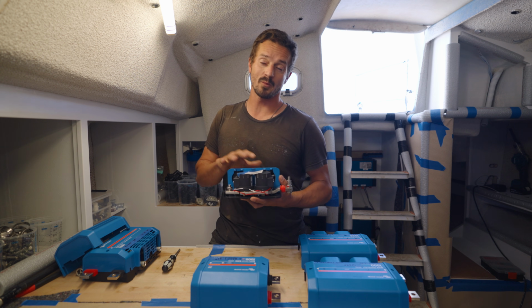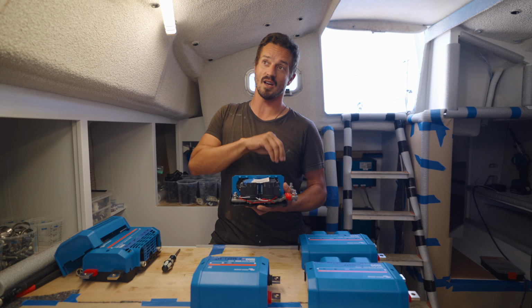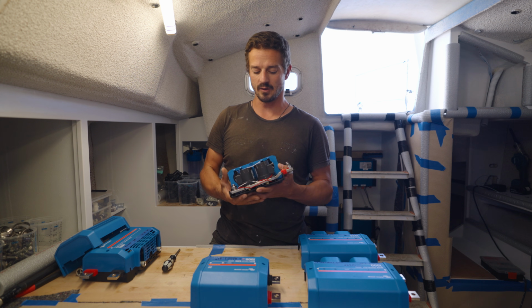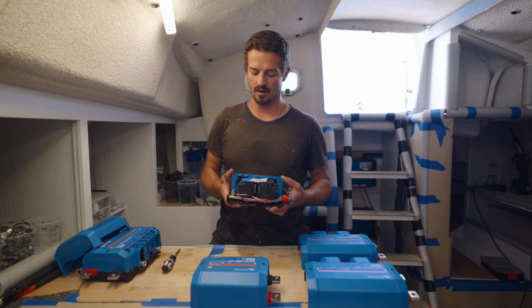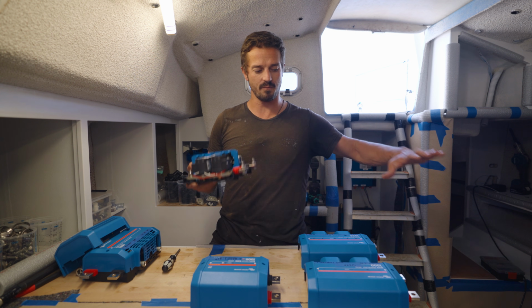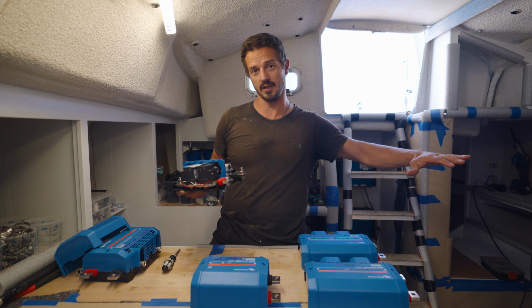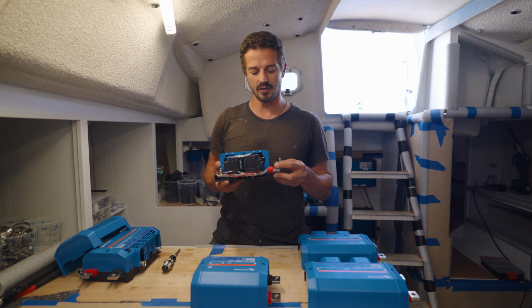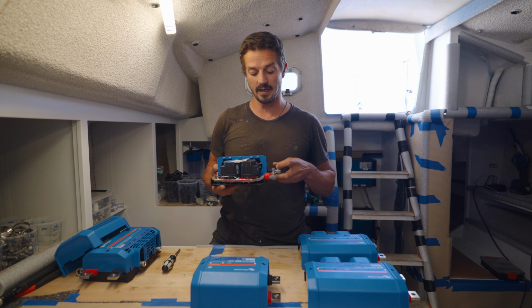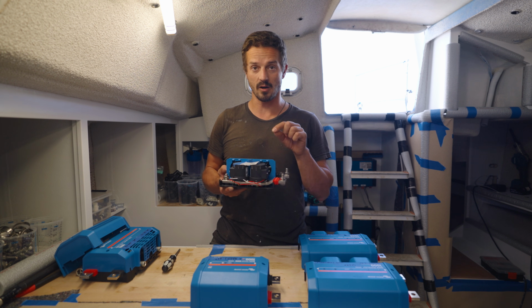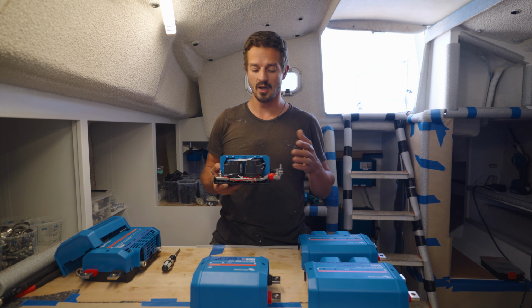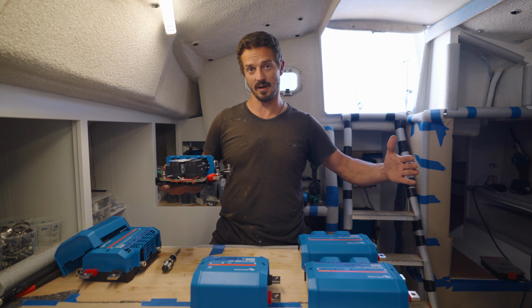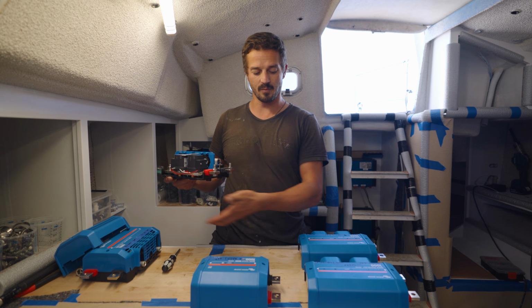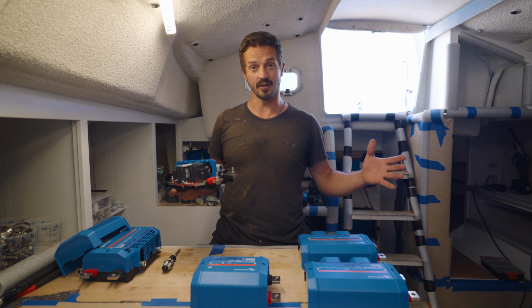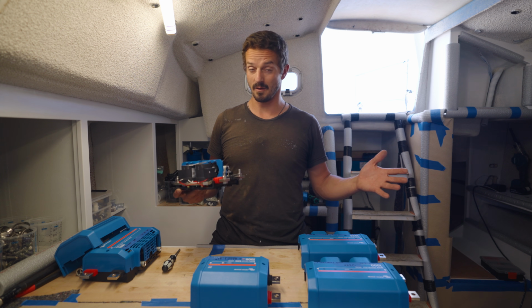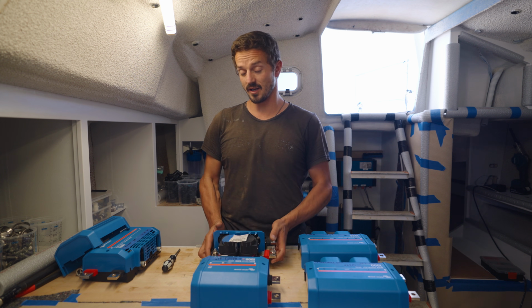The other cool part, which made us change our design a little, is that when we first started speccing our system, we were going to have each BMS individually split on each battery bank. Since then, Victron's come up with a software update and a small hardware modification - you just have to flip two wires - so that we can put both of these BMSs on either side of this big long bus bar, and everything's in one place. It's going to be much cleaner and much easier to troubleshoot. So that's changed our design a little bit.